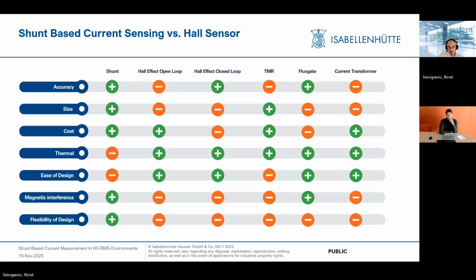So shunts do interfere with the circuit, but in the end you have a better accuracy. The size is small. If you really compare apples to apples, the cost is low. Total cost of ownership varies much if you compare with the Hall sensor. The shunt in itself is cheaper, but with the other components, it's somewhat the same. But it doesn't change the fact that you have to deal with saturation issues and possibly the parasitic effects of dealing with electromagnetic fields with the Hall effect.